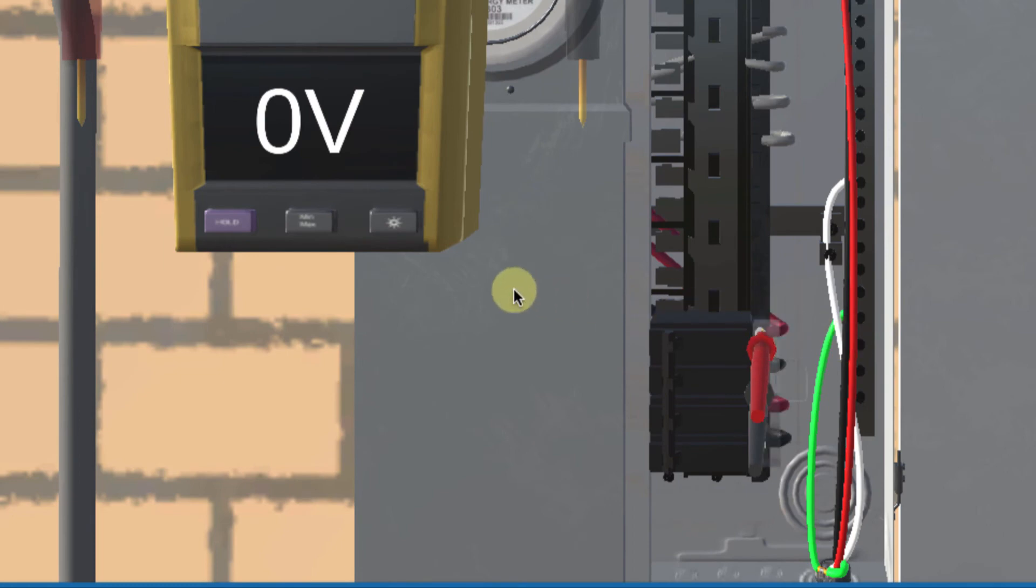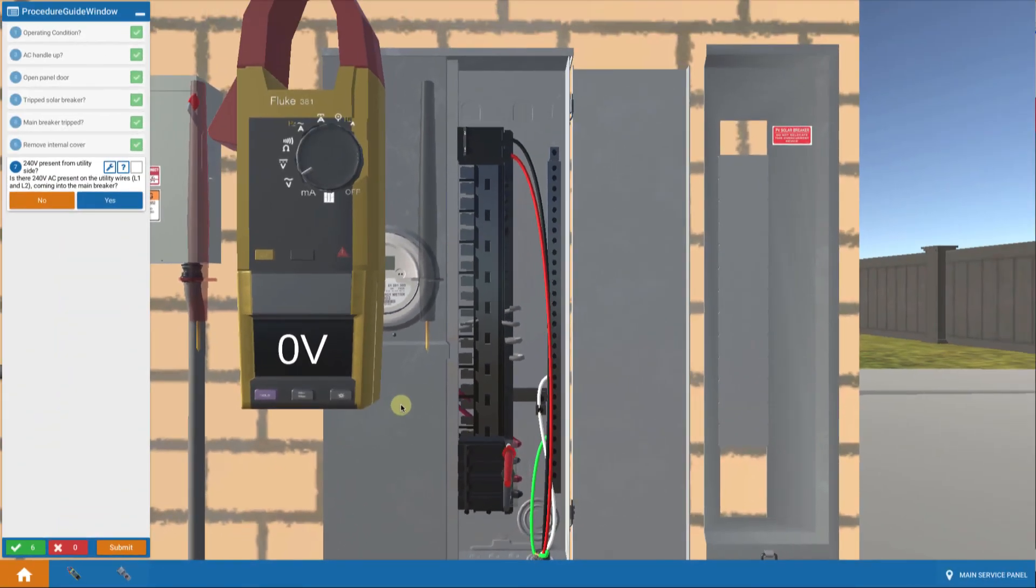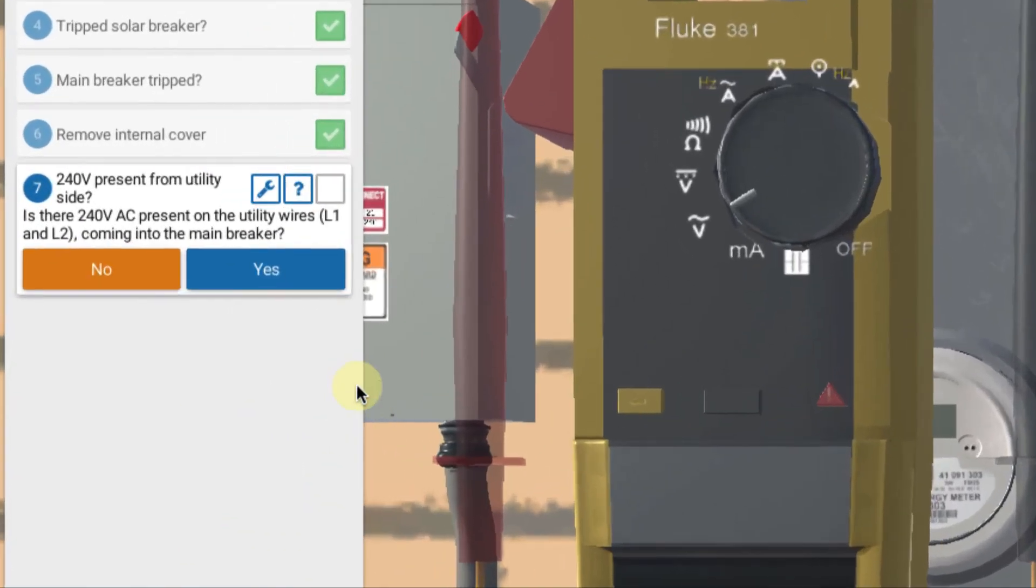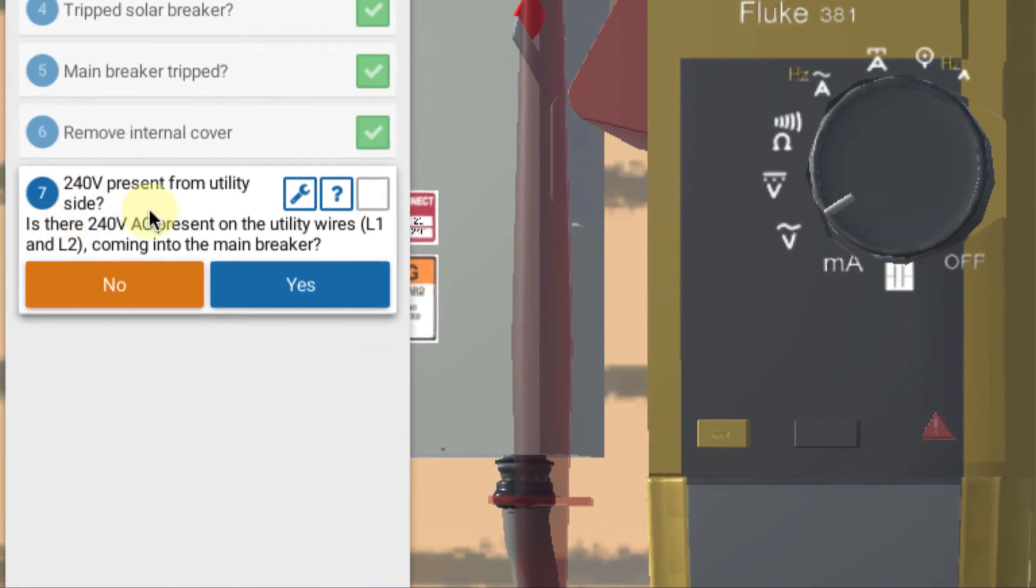Okay, that's not right. That's supposed to be 240 volts AC from the utility. But at this point I'm getting zero volts feeding into my main breaker. That's wrong. That means I have a problem on the utility side. So is there AC voltage present? The answer is no.